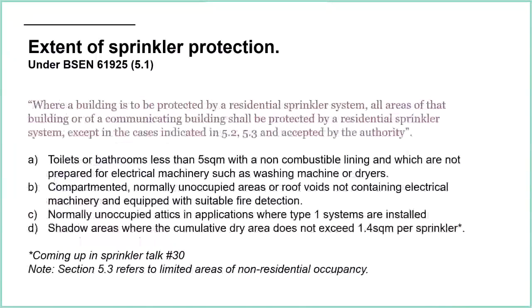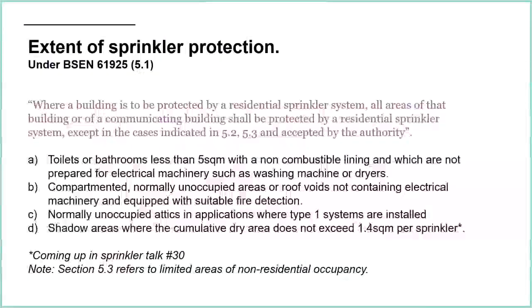There's a similar statement in 16925: where a building is to be protected by a residential sprinkler system, all areas of that building or of a communicating building shall be protected by a residential sprinkler system. Generally speaking, we want all areas to be protected except in the following cases and as accepted by the authority. Toilets or bathrooms up to five square metres are excluded, with additional detail in this standard specifying non-combustible lining and not prepared for electrical machinery such as washing machines or dryers. So they make the distinction that if your bathroom is also a utility room with other equipment, you should continue to sprinkler protect it.